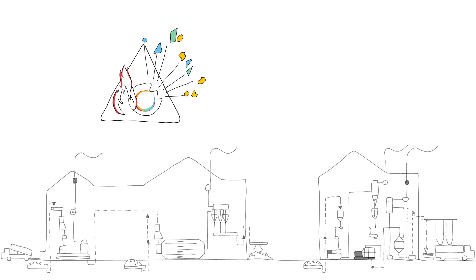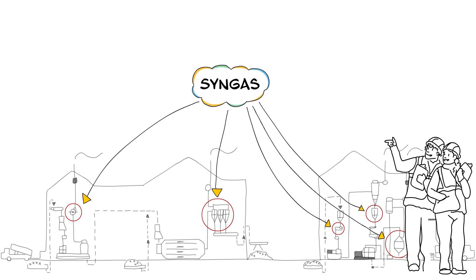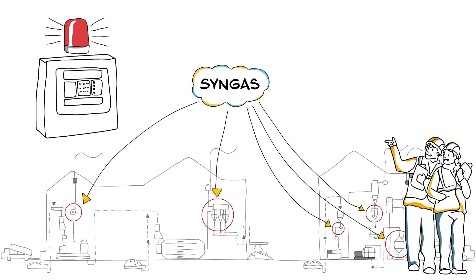So how can we reduce the risk of fire or explosion? The production of syngas can be highly complex, and syngas can accumulate in multiple places within the system. The accumulation of soot in the ducts may also be a source of fire. Operator vigilance and an intelligently designed alarm and control system are crucial in reducing the risk of syngas fires and explosions. Conduct a risk assessment to determine when and where syngas may accumulate and which control options will be most effective at managing the risk.